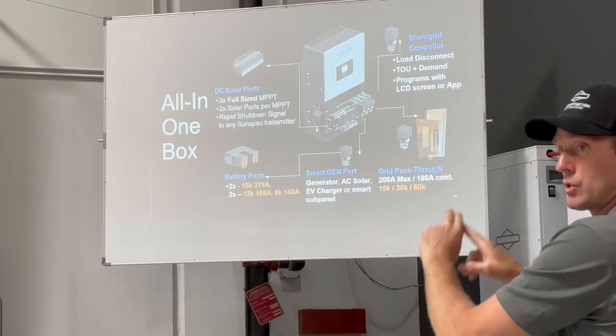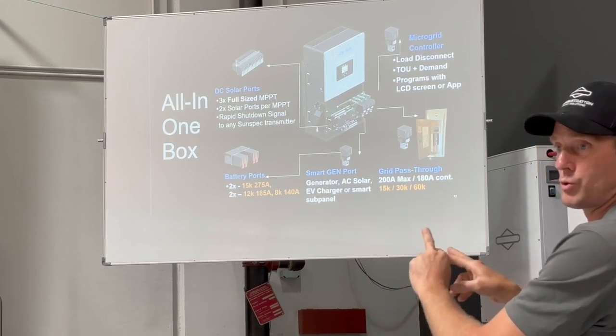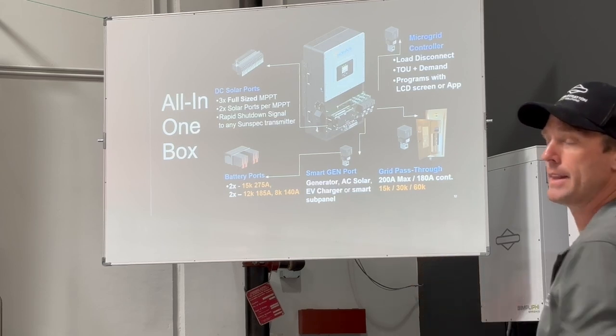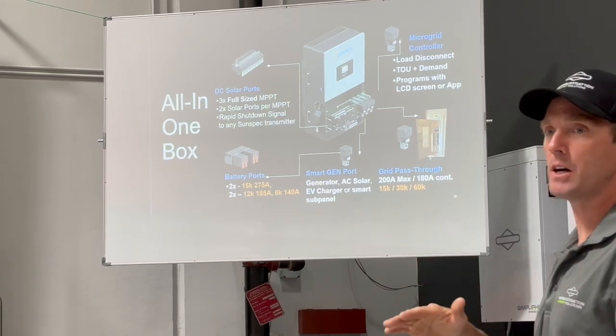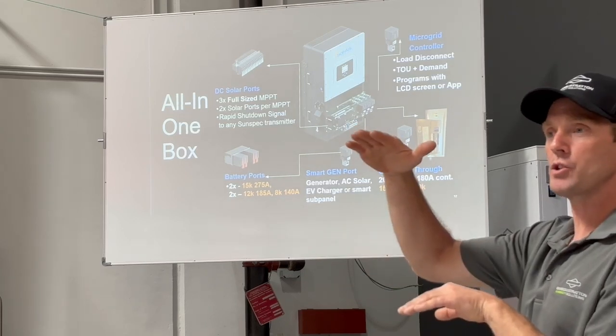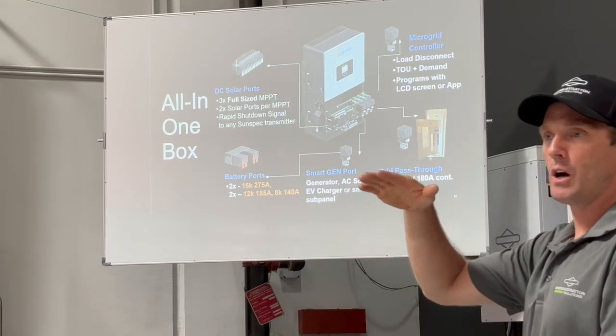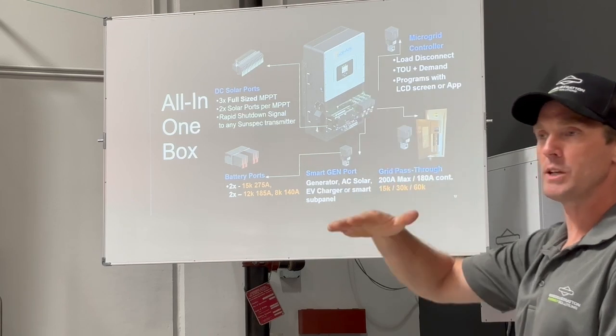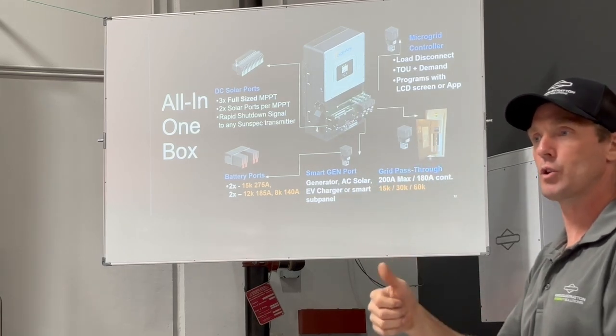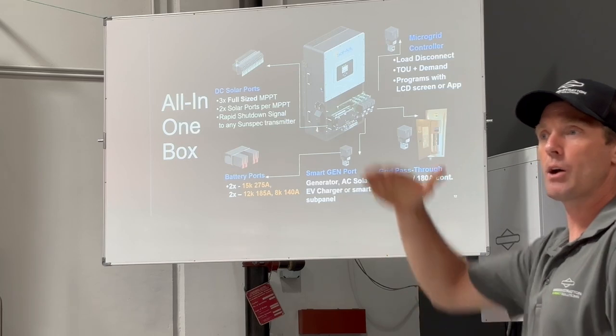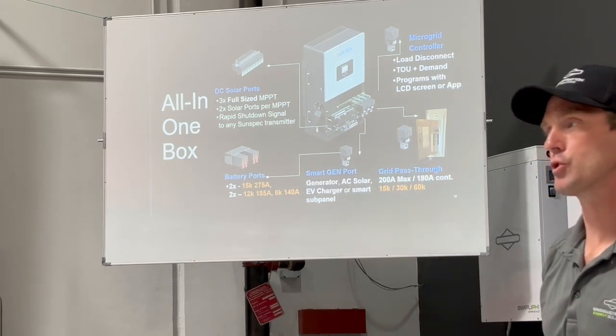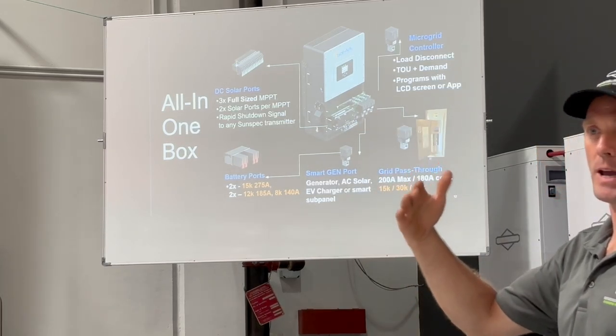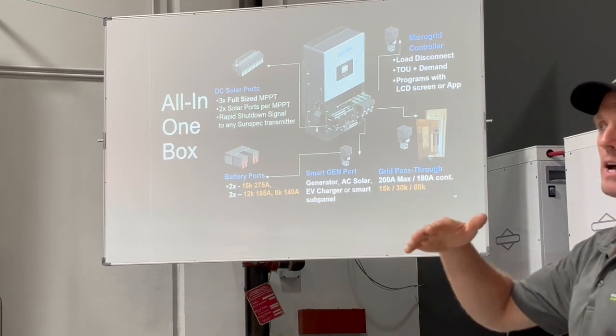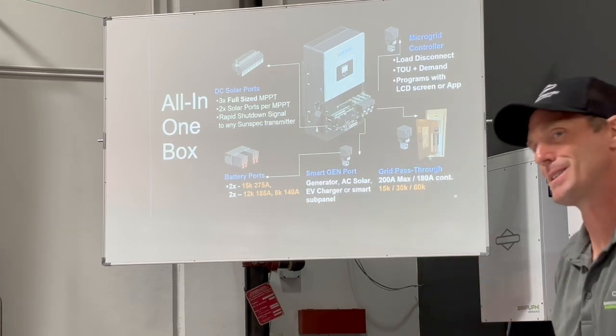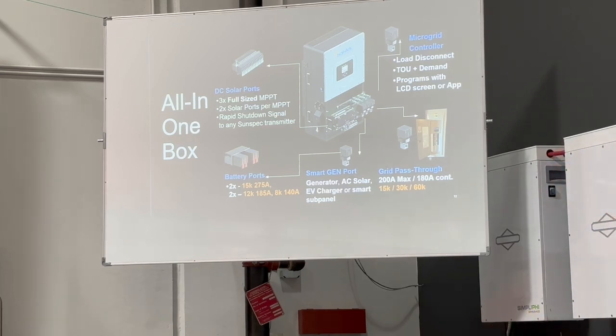Input number 2, match the voltages that are going into input number 2 if you have 2 strings going there. That's because what the MPPT does is it increases the voltage a little bit and sees what happens to the current. So it's constantly increasing and decreasing the voltage to optimize the product of current times voltage, which is power. That's how it does the power tracking. You need to have panels with similar voltages, otherwise it's not easy for the MPPTs to optimize the power output. But you have 3 independent ones, and number 1 does not have to match 2, and 2 doesn't have to match 3.